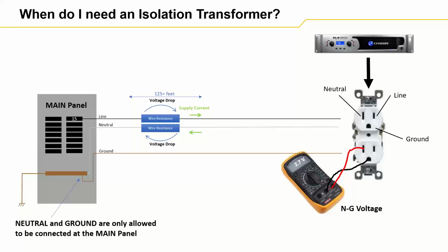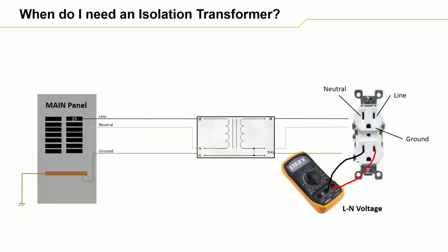So if you had other equipment plugged into this outlet, or possibly another outlet on this branch circuit, which is very standard practice in a lot of electrical installations, that second piece of equipment would see this neutral to ground voltage. Often, if a neutral to ground voltage is caused by a piece of equipment, that piece of equipment doesn't respond to it, but sometimes another one does, and it depends on the equipment. Especially if it's microprocessor-based equipment, it could be sensitive to these neutral to ground voltages, and that's where problems occur.